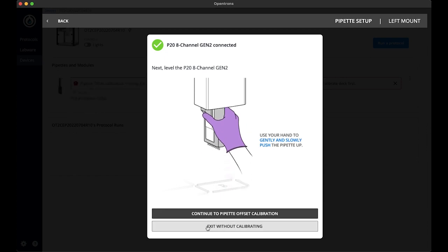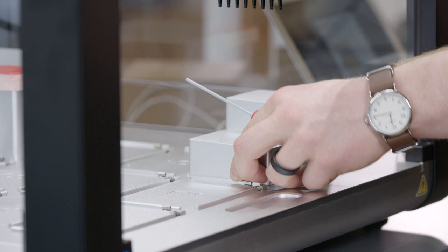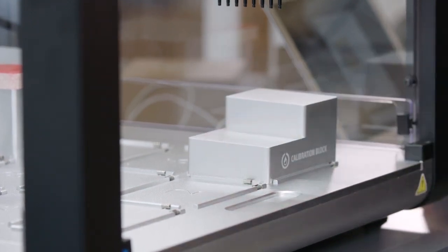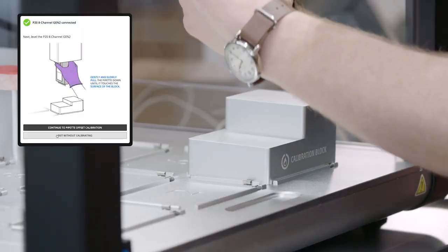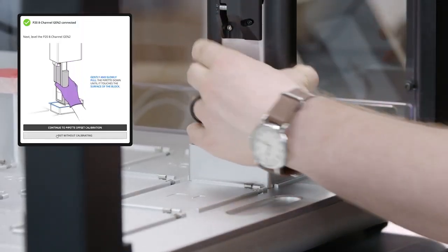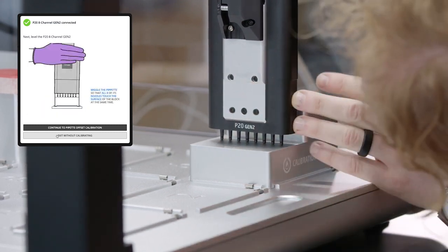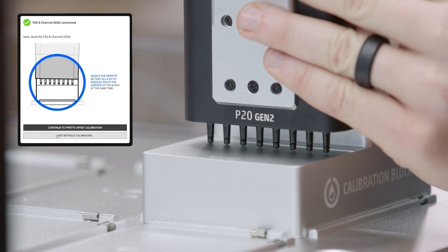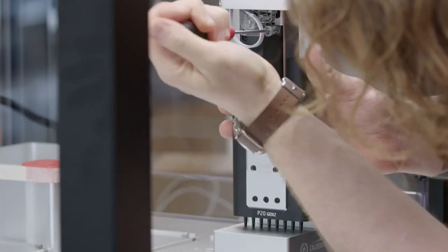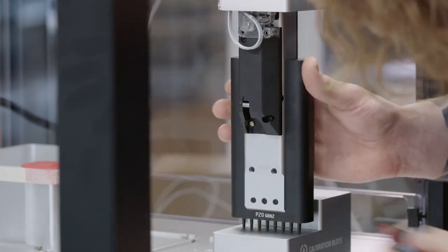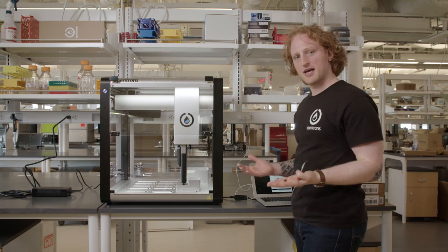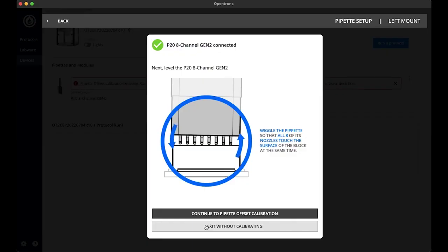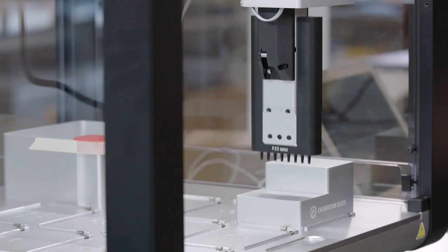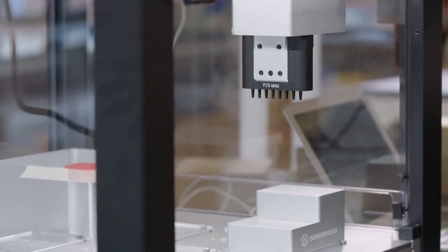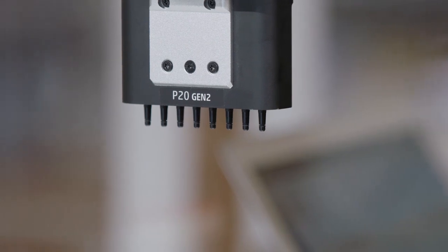I will now need to level the pipette. I will place the calibration block in slot 3, making sure that the short side is on the left side, and I will lower the pipette, and I can wiggle it until all the pipette nozzles are touching the calibration block. It's in a good location, so we'll go back and tighten the screws. So now that the pipette is attached and it's recognized and it's level, I'm going to exit without calibrating. I'm going to perform the pipette offset calibration and tip length calibration for both pipettes in the next video.